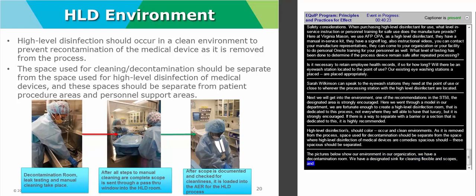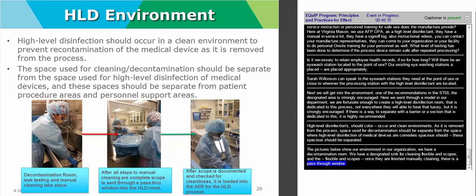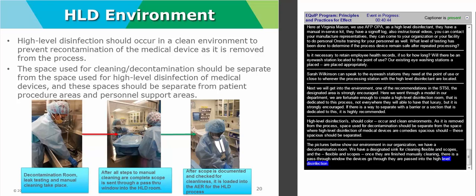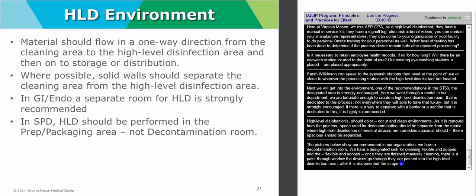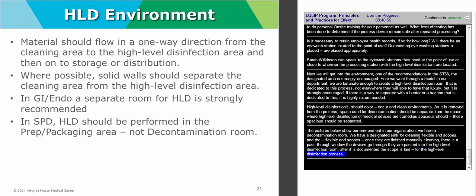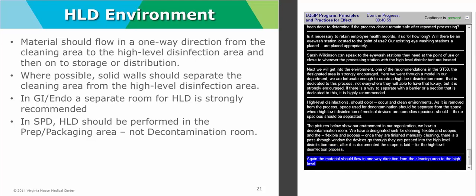This is where leak testing is performed and the manual cleaning takes place. Once they're finished manually cleaning, these devices go through a pass-through window and are passed into the high-level disinfection room. After the scope is documented and checked for cleanliness, it is loaded into our AER for the high-level disinfection process. Again, material should flow in a one-way direction from the cleaning area to the high-level disinfection area, and then on to storage or distribution.